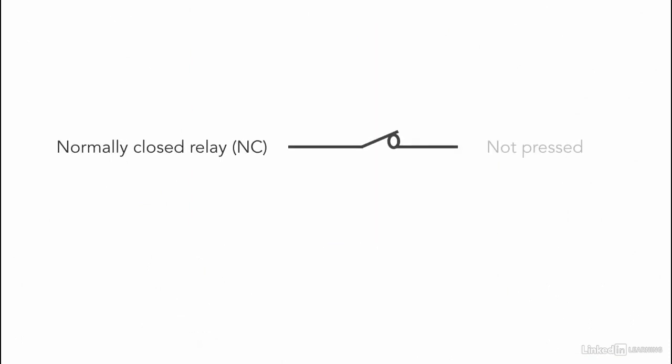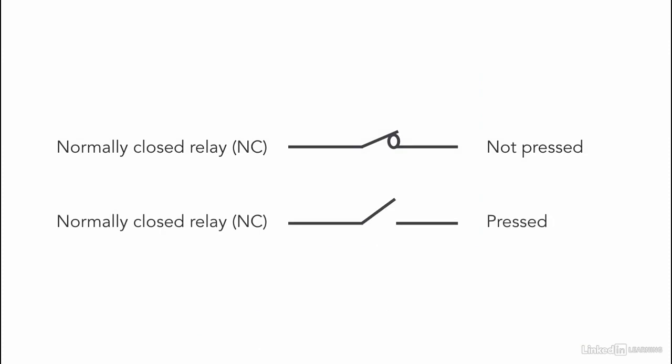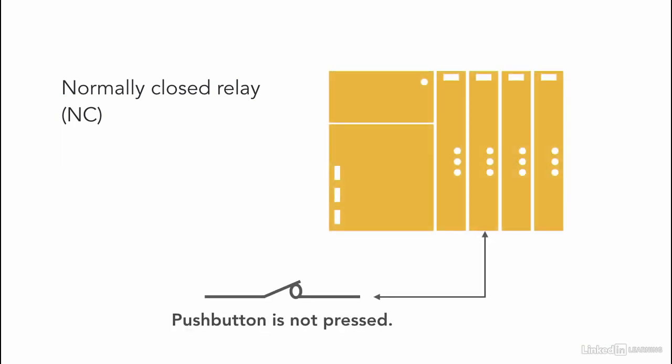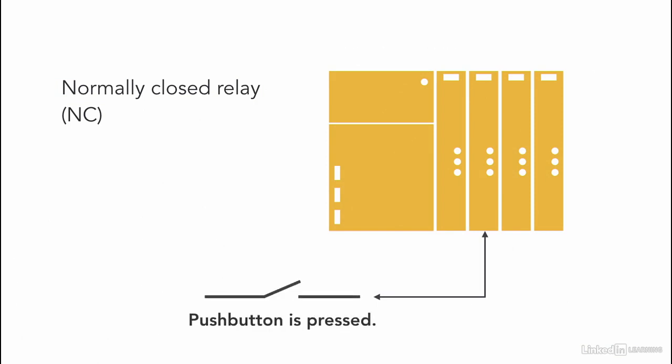For a normally closed contact push button, if the push button is not pressed, the memory location connected to that push button within the module is showing 1. As soon as the push button is pressed, the continuity changes, and then the memory address changes its state to 0 — there is no physical continuity.